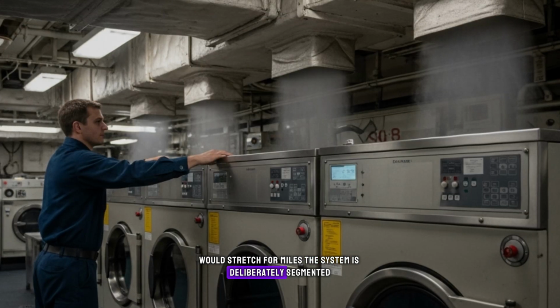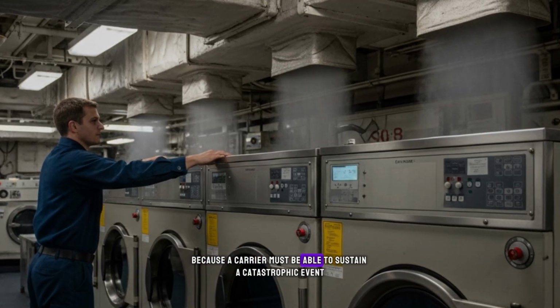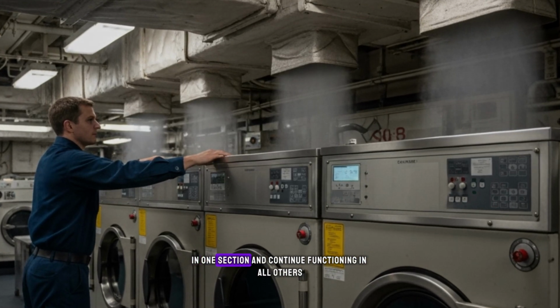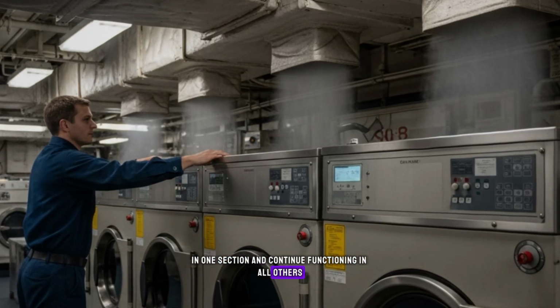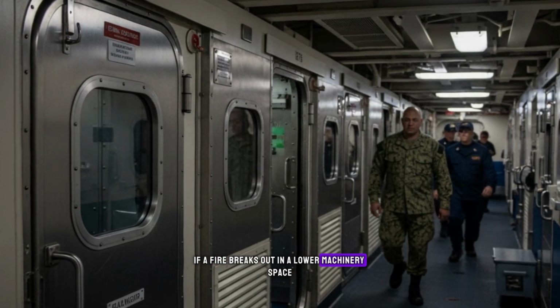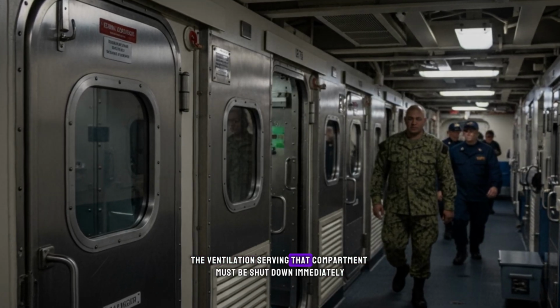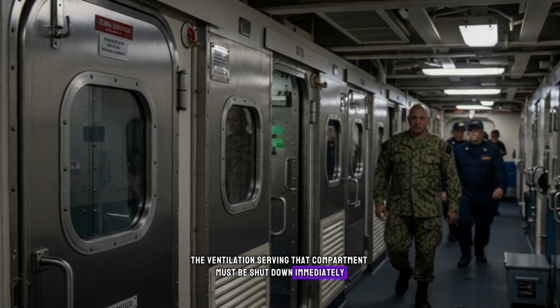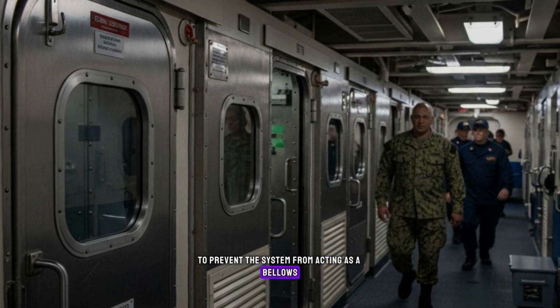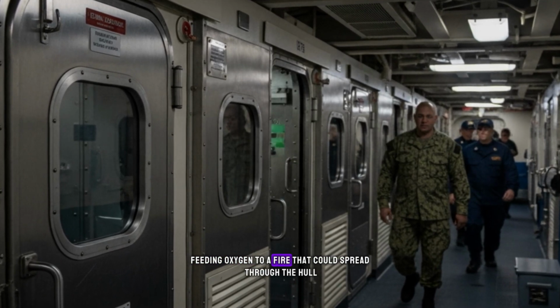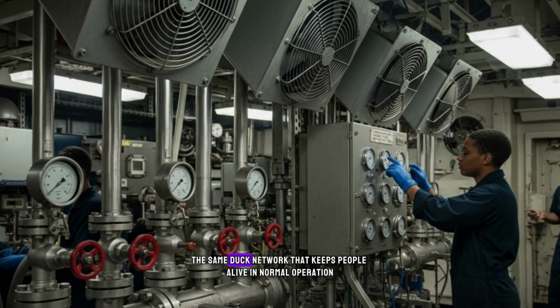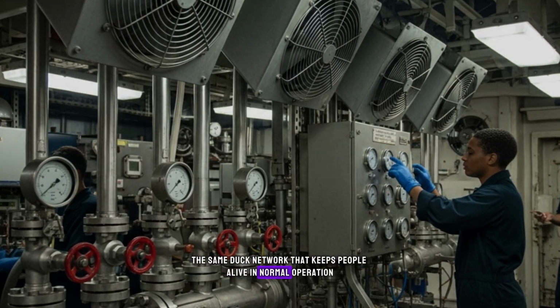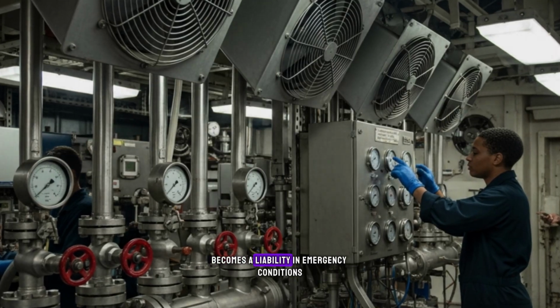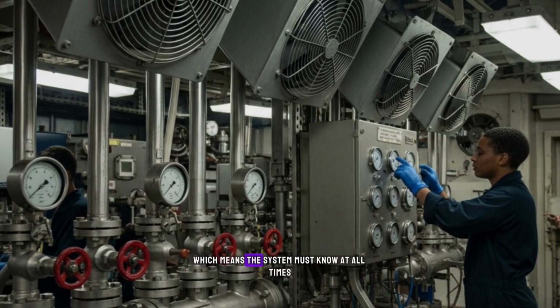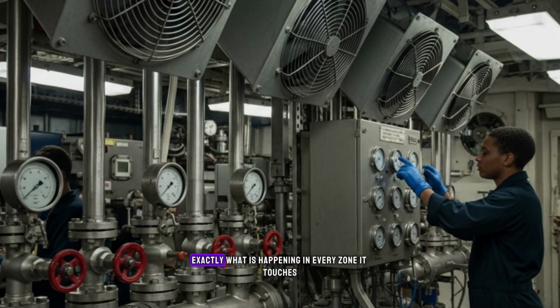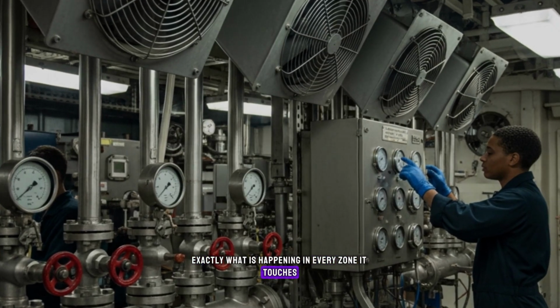The system is deliberately segmented because a carrier must be able to sustain a catastrophic event in one section and continue functioning in all others. If a fire breaks out in a lower machinery space, the ventilation serving that compartment must be shut down immediately to prevent the system from acting as a bellows, feeding oxygen to a fire that could spread through the hull. The same duct network that keeps people alive in normal operation becomes a liability in emergency conditions, which means the system must know at all times exactly what is happening in every zone it touches.